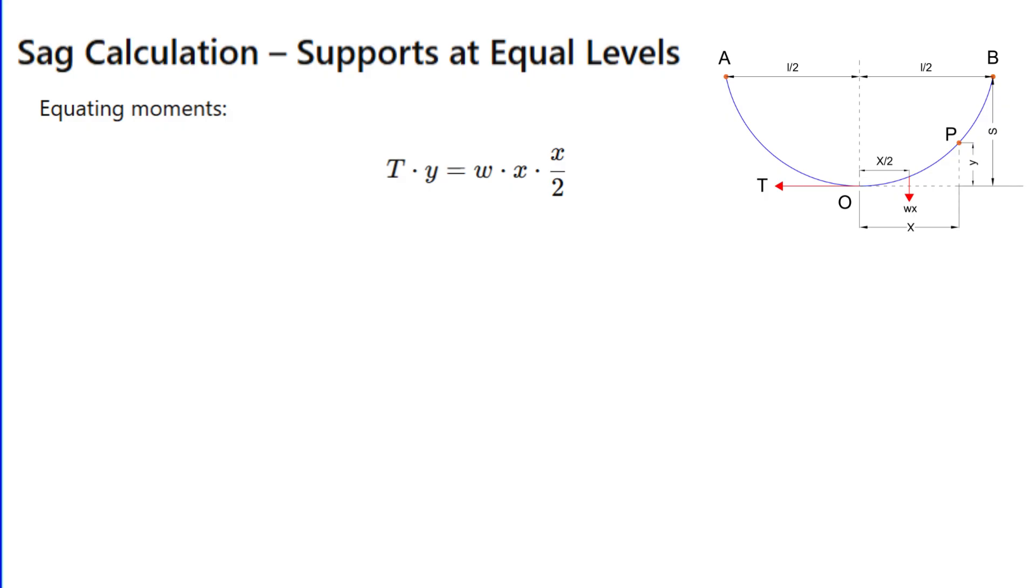Equating moments: T times y equals w times x times x/2, so y equals wx²/2T. Now at the support A, x equals l/2 and y equals sag s. Therefore, sag s equals wl²/8T. That's our famous sag formula for equal level supports.